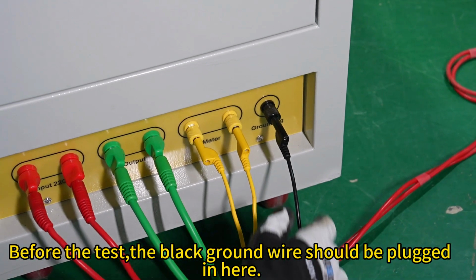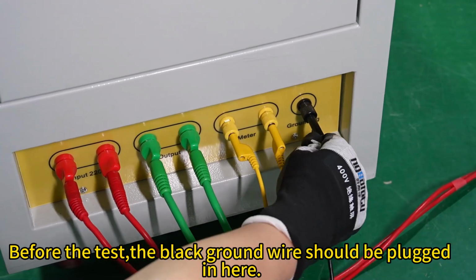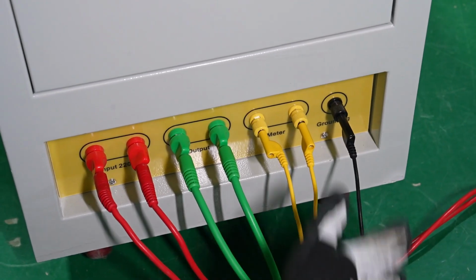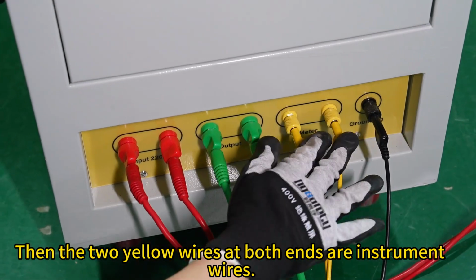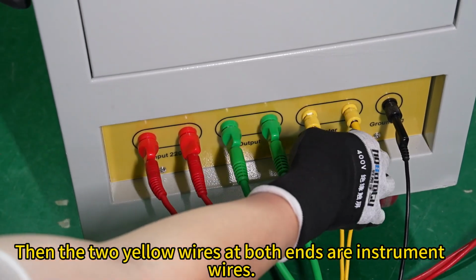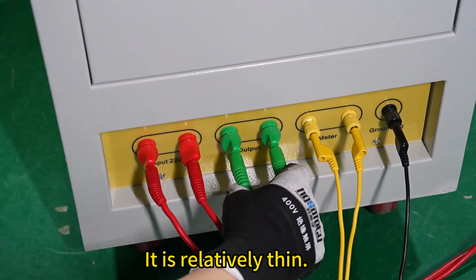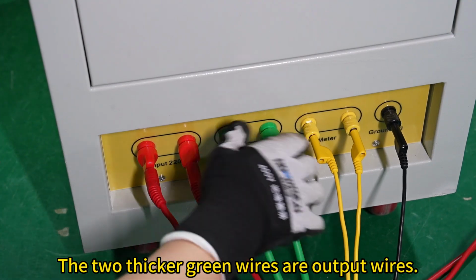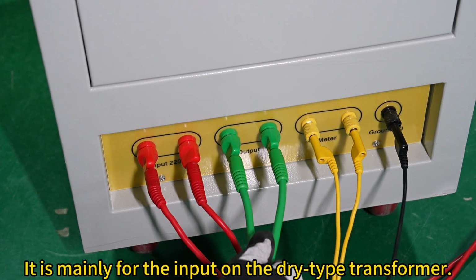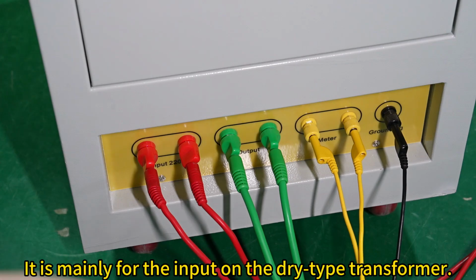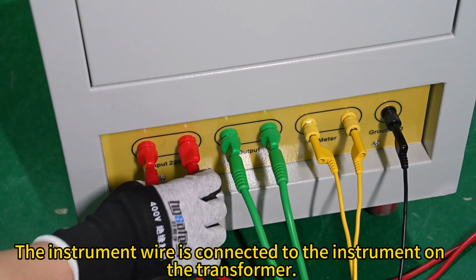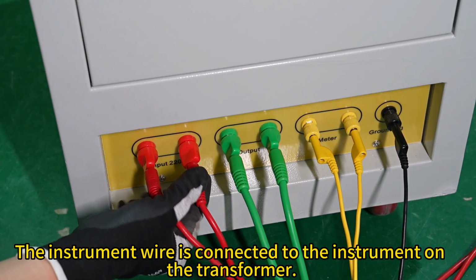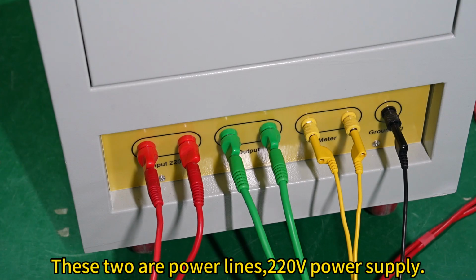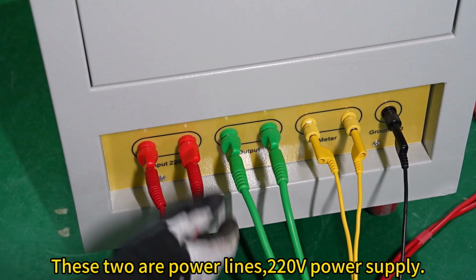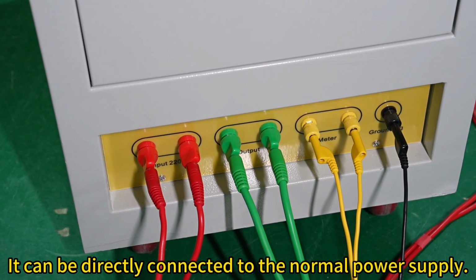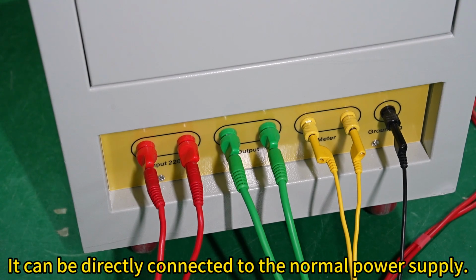Before the test, the black ground wire should be plugged in here. Then the two yellow wires at both ends are instrument wires. They are relatively thin. The two thicker green wires are output wires, mainly for the input on the dry-type transformer. The instrument wire is connected to the instrument on the transformer. These two are power lines, 220 volts power supply. It can be directly connected to the normal power supply.